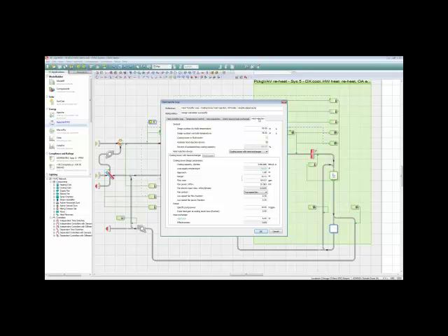The heat transfer loop is then effectively operating as a condenser water loop, and there really is no water side economizer mode. However, the heat transfer loop can, of course, move heat from a zone which is in cooling mode to another zone or zones which are in heating mode, which can extract heat from the very same loop. So it has the common loop functionality similar to a variable refrigerant flow system or VRF system. Does that answer your question pretty well?